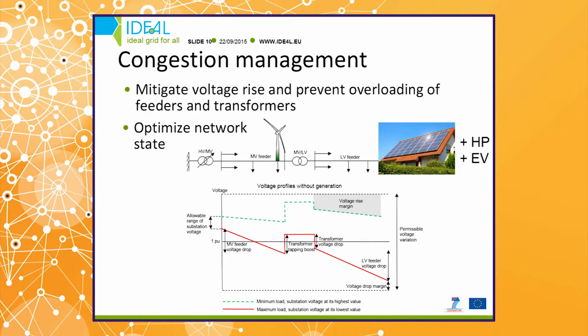The aim of congestion management algorithms is to mitigate congestions in the network. These can be voltage problems - DG units increase the network voltage, and with current planning principles the voltage rise often gets too large. Overloading of feeders or transformers is also possible, and the algorithm takes that into account too. The secondary objective of the algorithm is to optimize the network state, but the most important thing is to mitigate these congestions and increase the hosting capacity of the network.